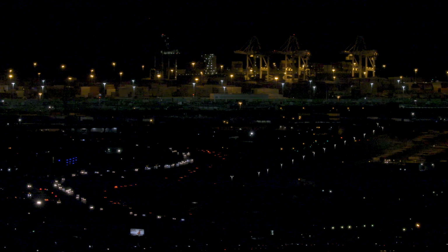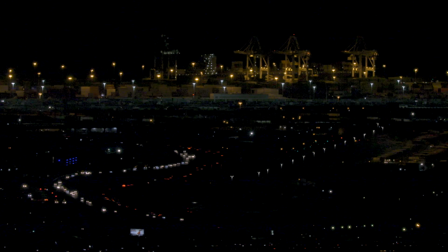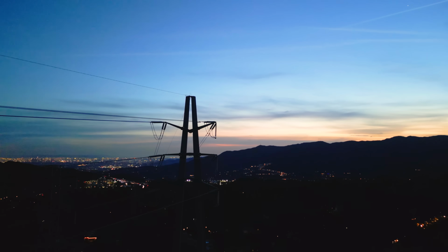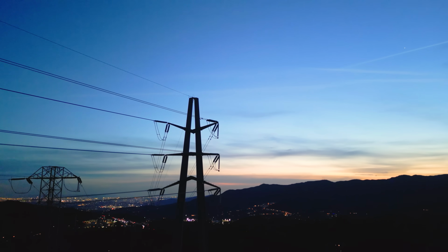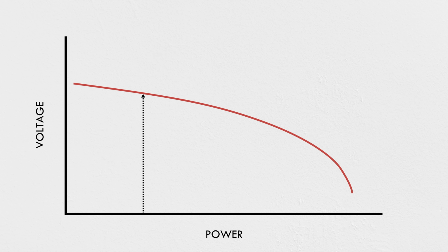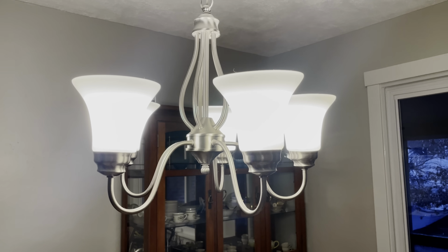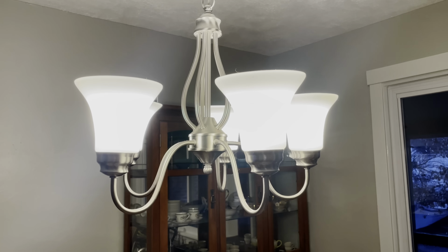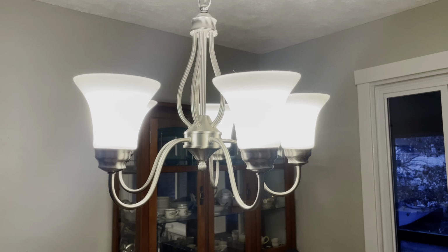But it's possible for the grid to collapse even if there's enough generation to meet the demand, because you still have to move that power to where it's needed over transmission lines. Engineers use a PV curve to keep an eye on this challenge. It relates the power flowing to a load on the system to the voltage it sees. As you would expect, the more power that flows, the more the voltage drops, since more power is lost on the transmission lines on the way to the load. It's the same reason the lights dim in old houses when the air conditioner kicks on. Current goes up, voltage goes down.